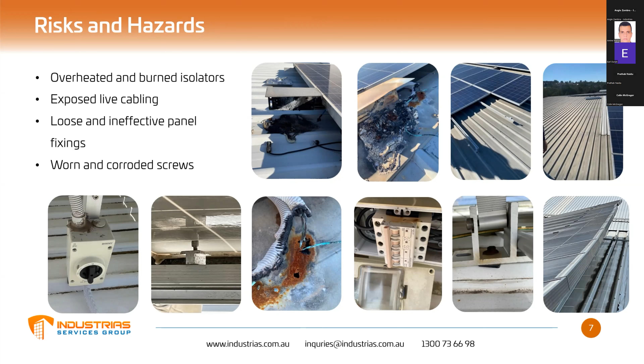Here you see non-compliances where conduit goes into the top of an isolator, making it more conducive to water ingress. There are burnt cables, browning componentry, bent and curved modules, and in the top right corner, corroded mounting that caused a solar module to actually fly off its mounting.